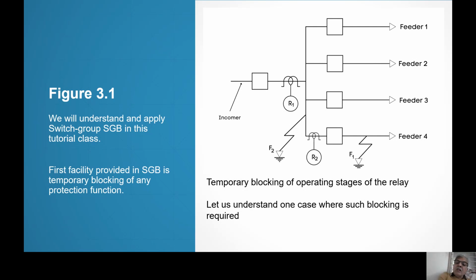Now if a fault occurs at F2 on the bus, then R1 will have to operate after 0.35 second only. Here, using this blocking feature, which is also known as reverse interlocking, the time discrimination margin between R2 and R1 can be reduced to 40 millisecond, 0.04 second. So R1 will operate just after 0.14 second. So R1 will operate very fast, a very good advantage. R1 will be very quick in operation.